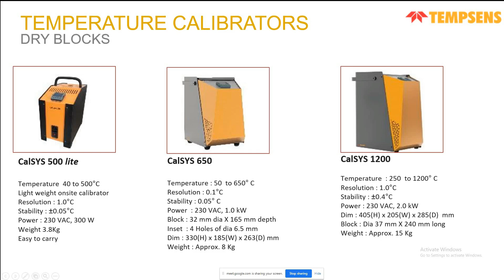These two items, 650 and 1200, are our most selling items. They go up to 650 degrees and 1200 degrees centigrade, mostly used for thermocouple and RTD calibration. These are laboratory models, going up to 1200 degrees centigrade, up to 1500 degrees centigrade, up to 1700 degrees centigrade for thermocouples. They can come with special versions. Right now what you are seeing is a single zone, but it can have a 3-zone heating and controlling system for better axial uniformity. So, according to customer requirements, we can cater to specific requirements for these calibrators.